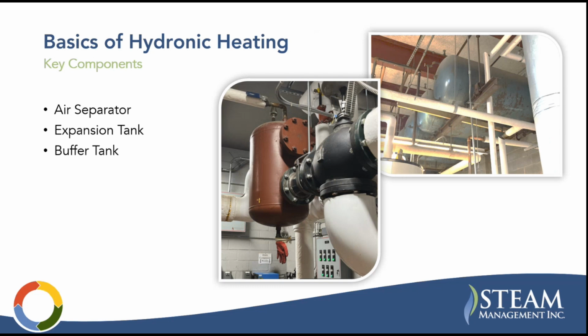You have an air separator to remove air from the system. That's very important. Air in a hot water system promotes corrosion and reduces the life of components. You have expansion tanks to allow fluid expansion as it heats and cools. And then you have a buffer tank to add volume to the system and give you some thermal inertia, which we'll talk about later.